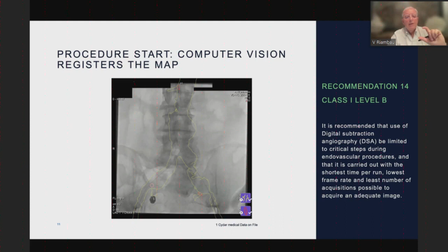So it is important to recognize that this overlapping is automatic on the table, and you don't need to perform any kind of pre-acquisition on table, just to have the possibility to look for two vertebrae at the level of the lumbar vertebrae, and then the fusion is automatic. As you can see here, even the software can accommodate the orientation or the position of the patient. If you compare the position of the patient in terms of the vertebral position during the CT, the software can correct the position on table during the procedure.